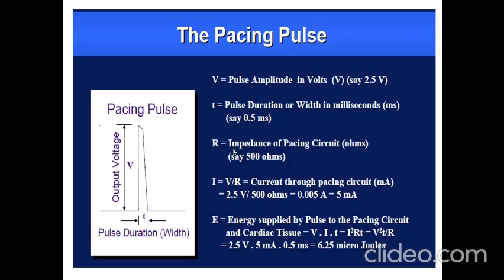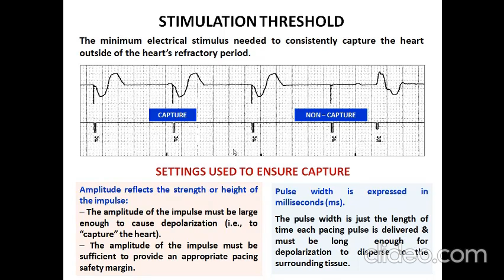And the stimulation threshold, as we already said, is the minimum electrical stimulus needed to consistently capture the heart outside the heart's refractory period. Just notice the diagram, we have the word capture. Capture means that in response to the stimulus, the heart starts working well. So that is called the capture area. Whereas if the cardiac activity is not initiated by the stimulus, then it is called the non-capture area. And the settings used to ensure the capture area are amplitude and pulse width. We discussed that amplitude reflects the strength or height of the impulse, whereas pulse width is represented in milliseconds. So the pulse width is just the length of time each pacing pulse is delivered. With respect to these two conditions, we can ensure the capture, the stimulus activity of the cardiac function.